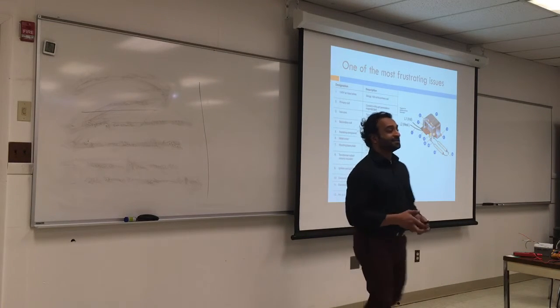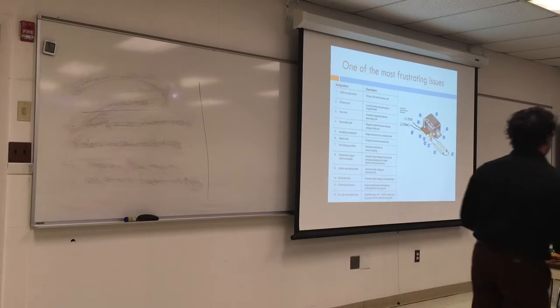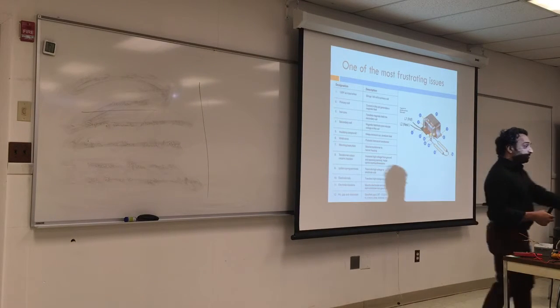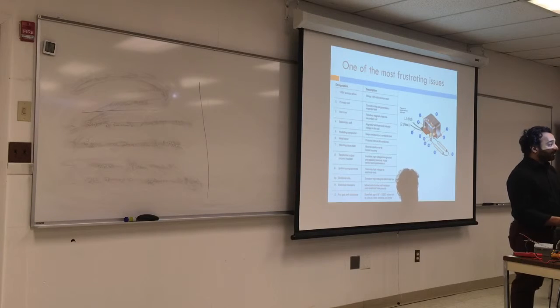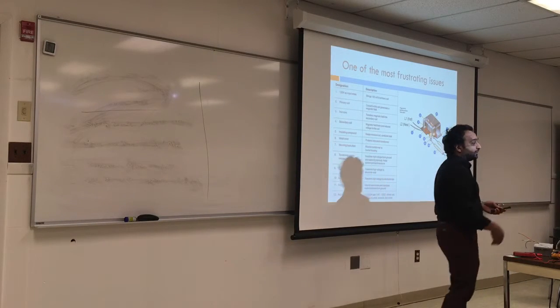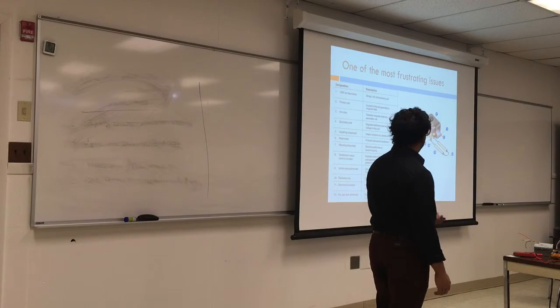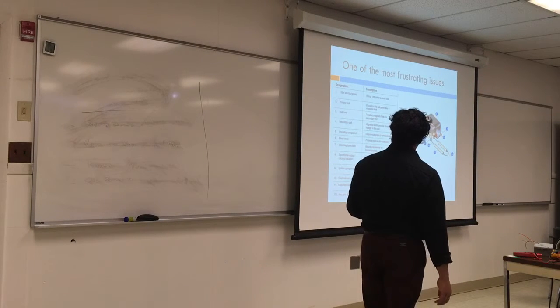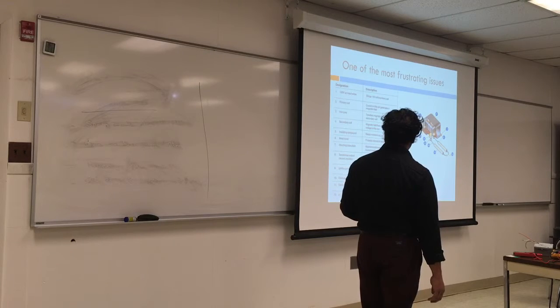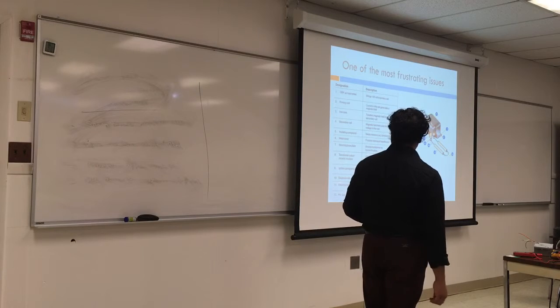The mounting, again, this is something a lot of people neglect. Make sure the mounting is sound and it sits completely where it's supposed to. It's not wedged sideways. Over time, these things get open and closed many times, and eventually they do not close properly. And if they do not close properly, probably they're not touching the electrodes, and that will give you less voltage at the output. Metal cover, mounting, output, that's something you can check with a high voltage tester.